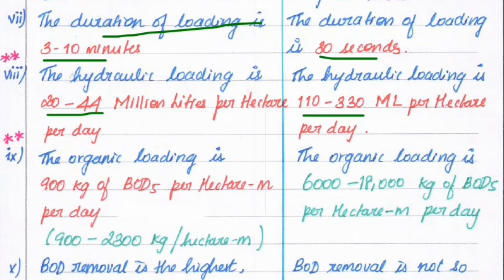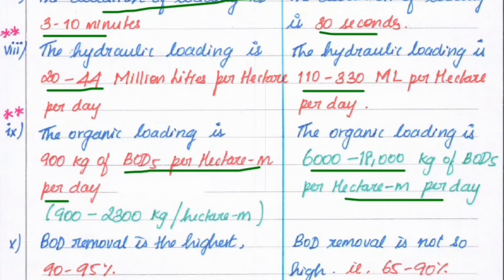The organic loading in the slow rate trickling filter is 900 kg of BOD5 per hectare meter per day, while in the fast rate trickling filter the organic loading is 6000 to 18000 kg of BOD5 per hectare meter per day. BOD removal in slow rate is highest at 90 to 95 percent, but in high rate trickling filter it is 65 to 90 percent.